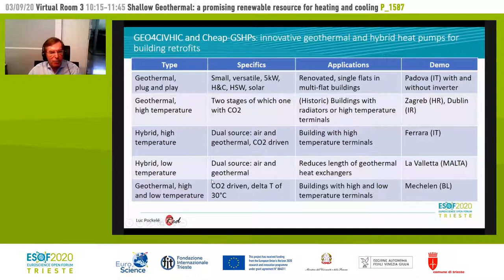The geothermal high temperature one is CO2-driven, my apologies - I'll continue on that. It is again the CO2-driven pump in a single stage, which needs a high delta T, but here we combine high and low temperatures. This is an application for buildings where you may be able to keep high temperature terminals, because otherwise you'd need to destroy too much piping or it's too costly, combined with an extension or a place where you can do low temperature terminals. They are put in series to create a higher delta T, so we can reach good performance with a geothermal heat pump at reasonable cost.